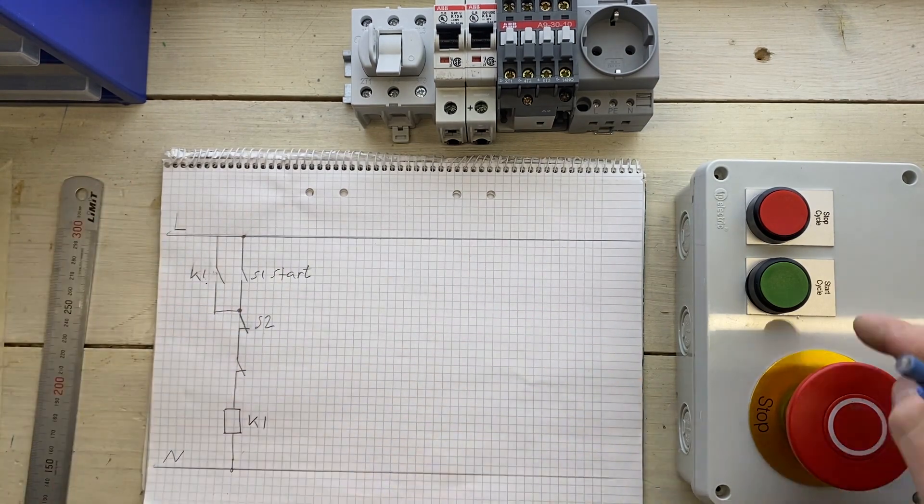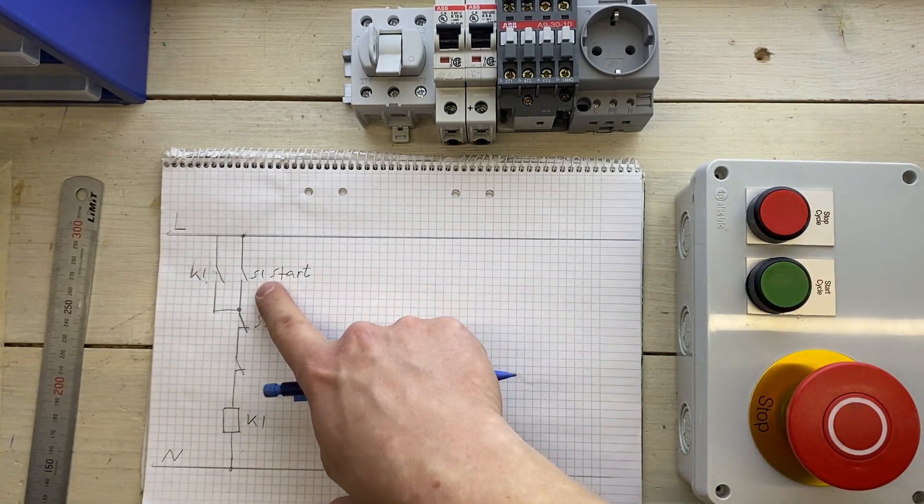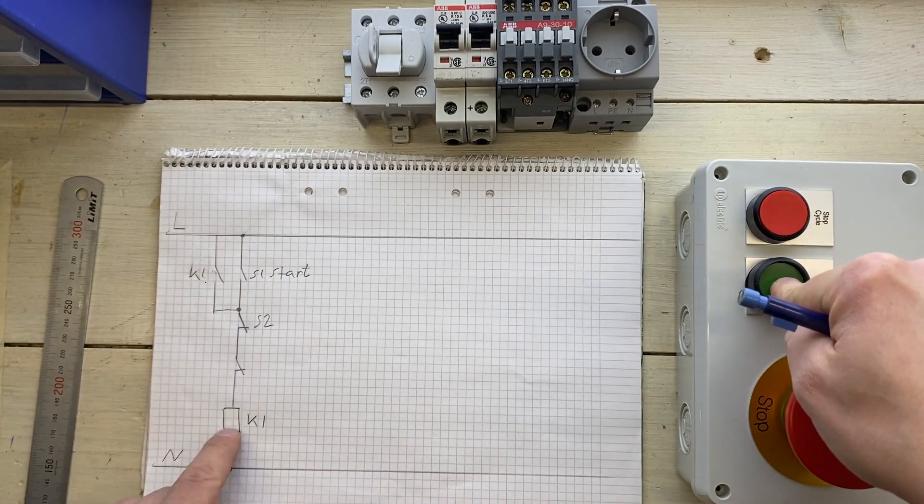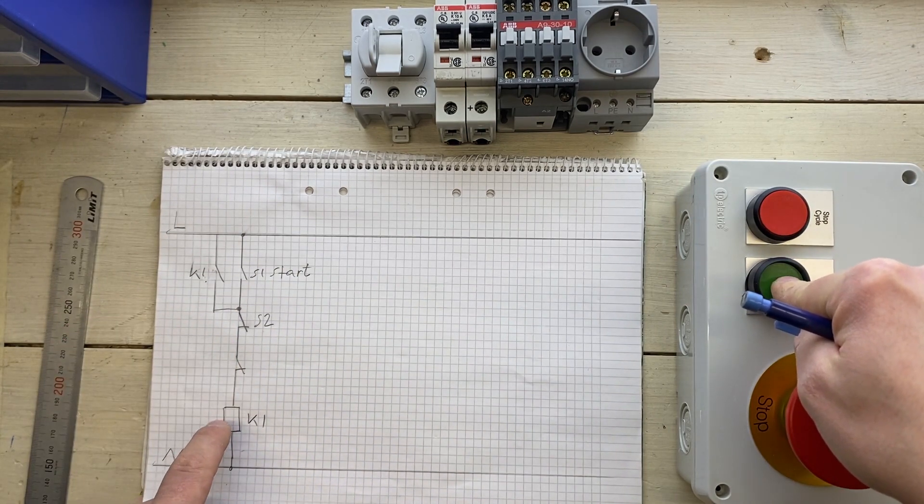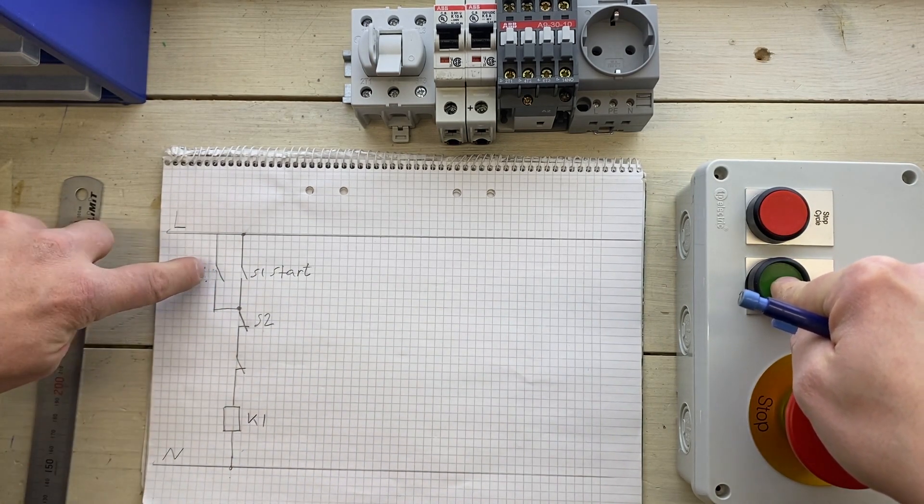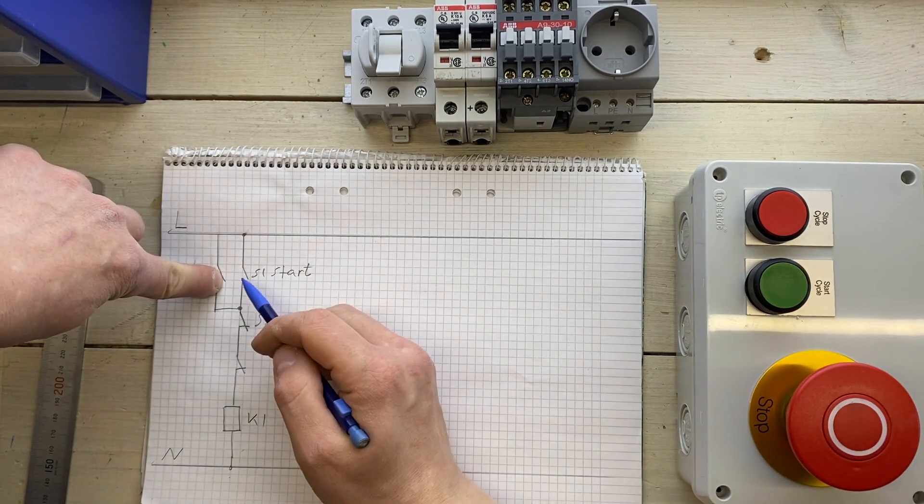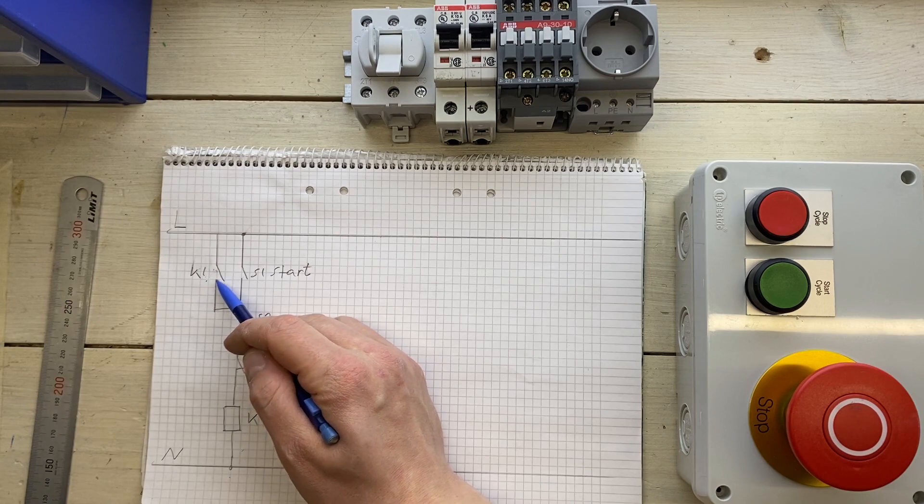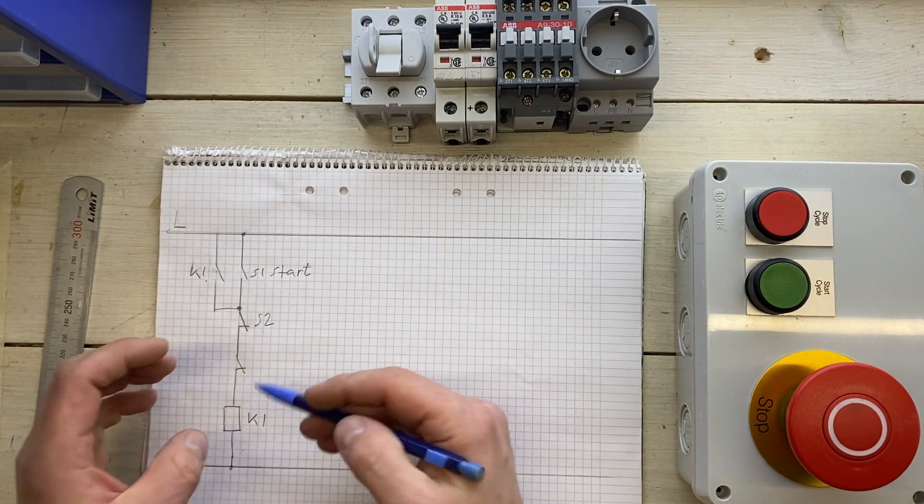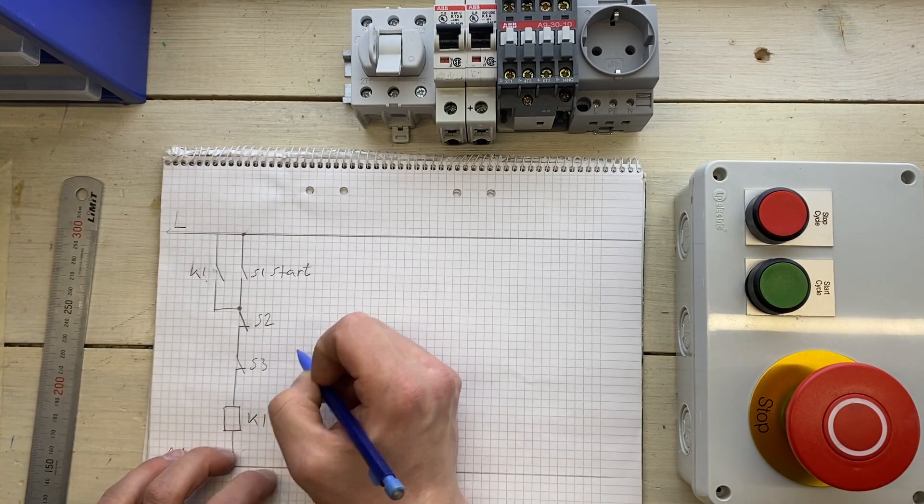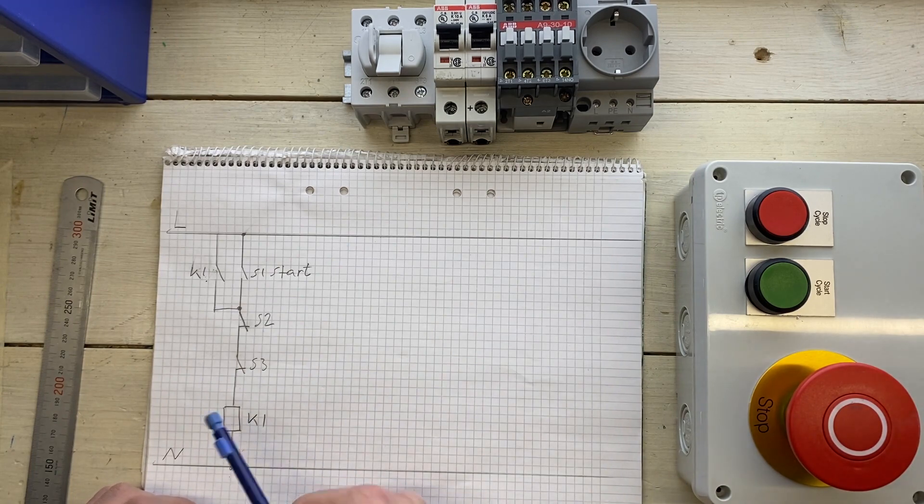So what will happen now when we push the start button? First off, start button will close. We will energize the coil. When the coil is energized, that one is closed. Which means that if we release the button, S1 opens again, but K1 is still closed. So now the relay is holding itself.